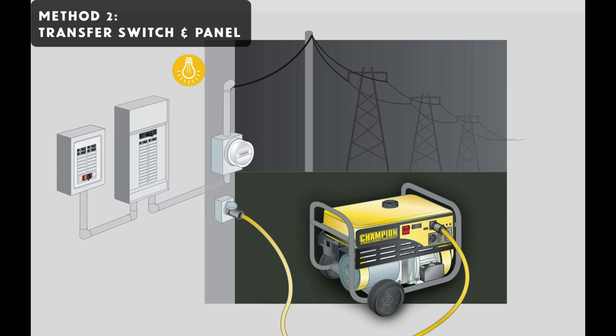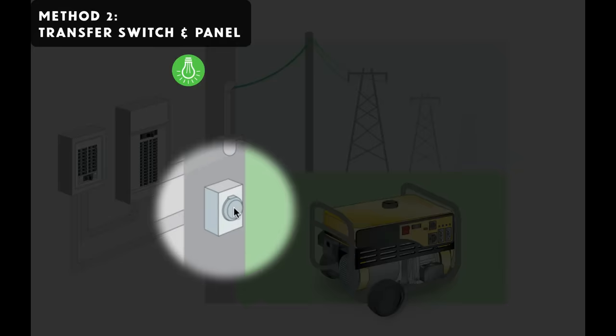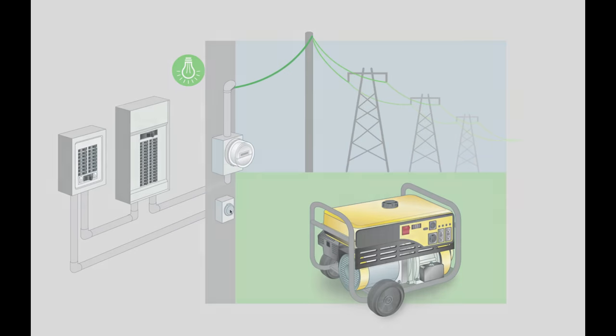And when the power is restored, you start by switching this switch back off again, back to the grid position, and then you shut off the generator and you remove the cable. And the little door here, the weatherproof door, is closed and everything's sitting, waiting for the next outage for you to connect your generator and get things working again.